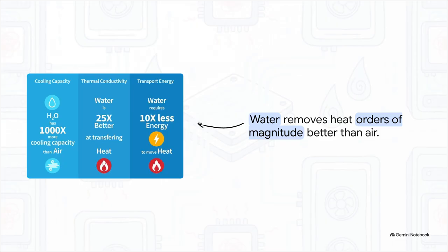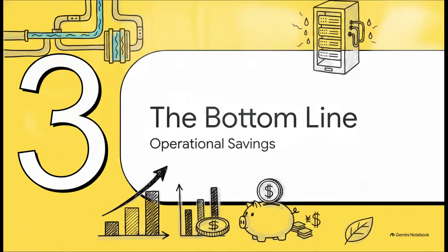Water actually has 1,000 times more cooling capacity than air. 1,000! And on top of that thermal conductivity advantage, it actually takes 10 times less transport energy to move that heat away. That means you're doing vastly more cooling work while spending significantly less electrical energy to do it. It's a huge win-win. All right, let's get into Section 3, the bottom line.